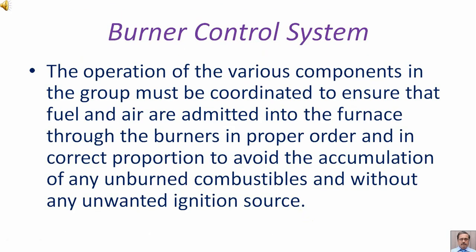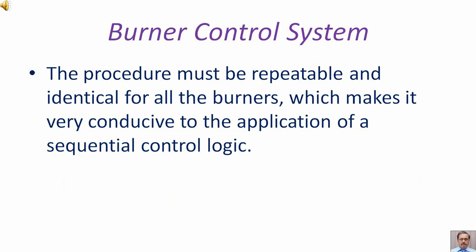The operation of the various components in the group must be coordinated to ensure that fuel and air are admitted into the furnace through the burners in proper order and in correct proportion to avoid the accumulation of any unburned combustibles and without any unwanted ignition source. The procedure must be repeatable and identical for all the burners, which makes it very conducive to the application of a sequential control logic.